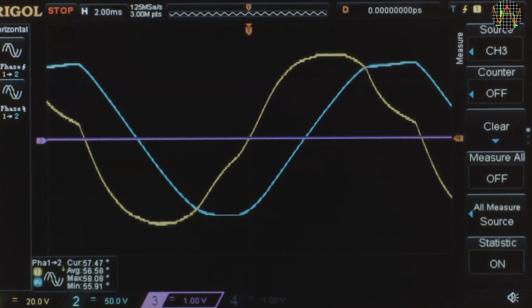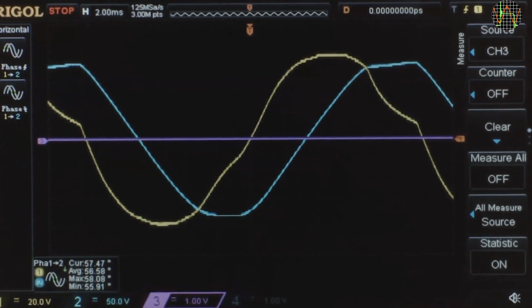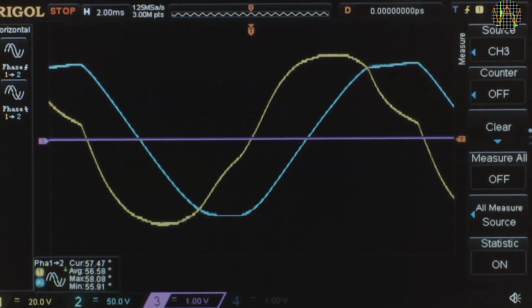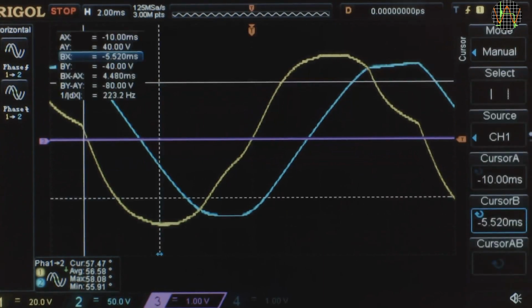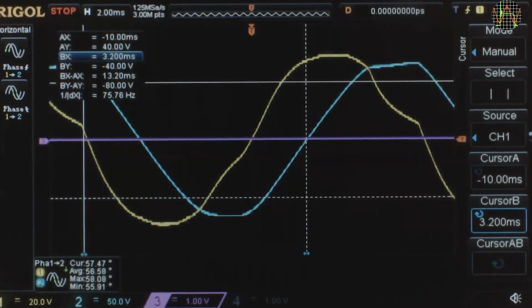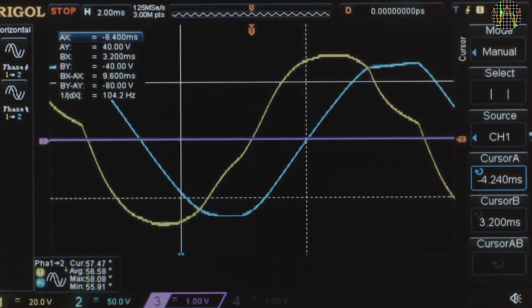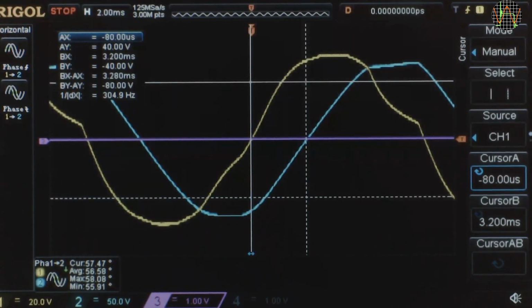Maybe the automatic measurement is a bit off due to the slightly distorted waveforms after passing through 2 transformers. So let's measure it manually using cursors. Basically we need to measure the time difference where the 2 curves cross through the zero line. So I move one vertical cursor to the point where the blue curve crosses. And then do the same with the other cursor for the yellow curve. The only thing we are interested in is the BX minus AX readout, which is 3.28 milliseconds.